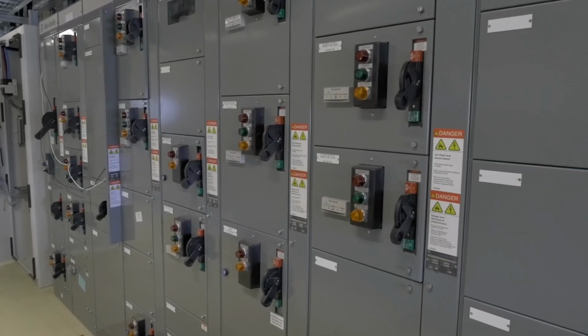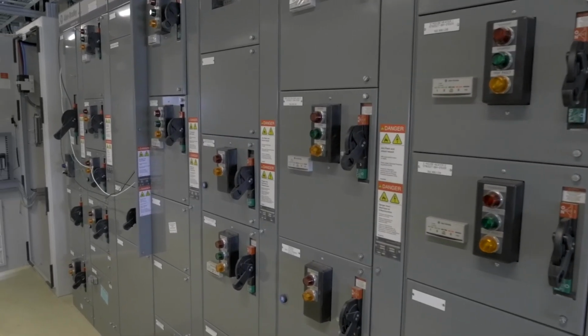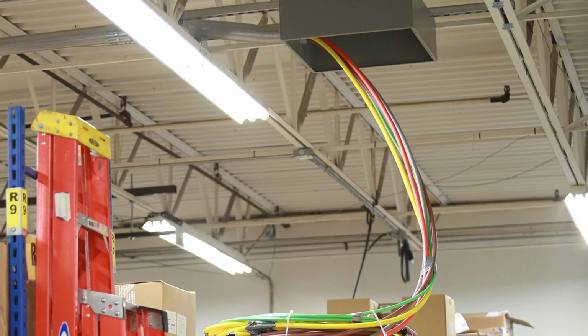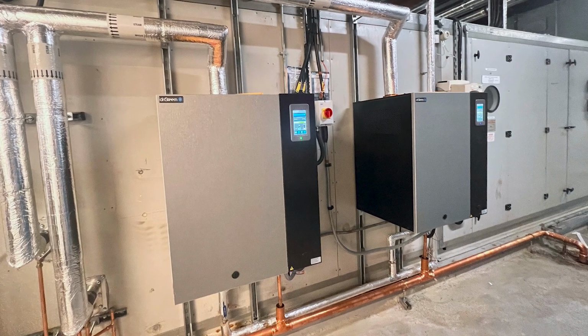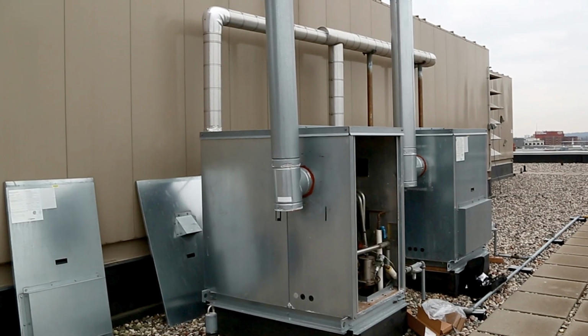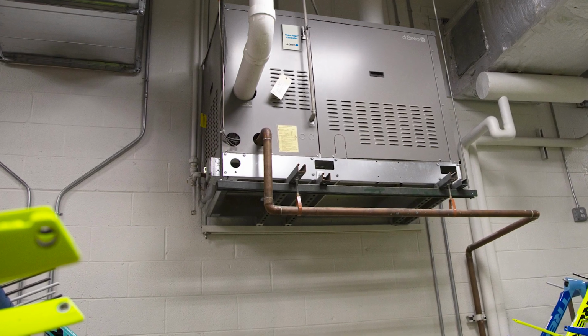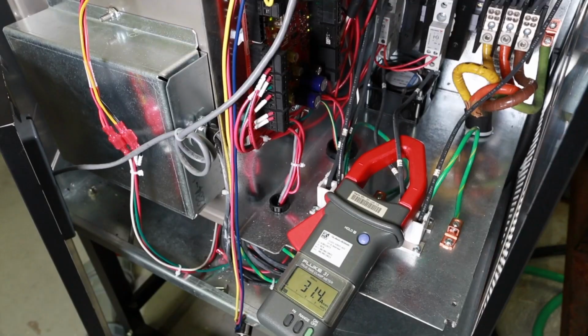Otherwise, you're thinking through, okay, what other utilities do I have available? Do I have electricity? If so, what is the voltage? What is the phase? I have to understand that. Do I have enough? And where is that located versus where I'd want to add the moisture? Or maybe it makes sense on a large capacity system to use natural gas. For a larger capacity system, you can do more with it. There's a lot of electrical current required sometimes to make steam, and doing it with a burner is a little more efficient. But you have to understand what I've got available and how I'm going to mitigate that. There are additional considerations you have to understand.